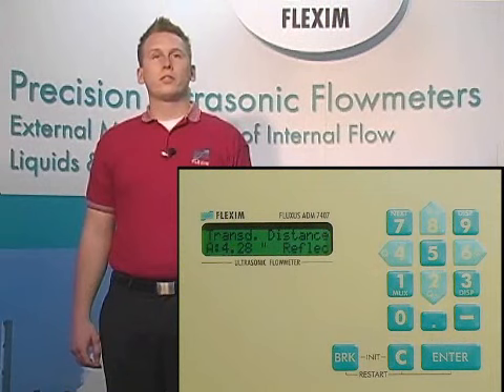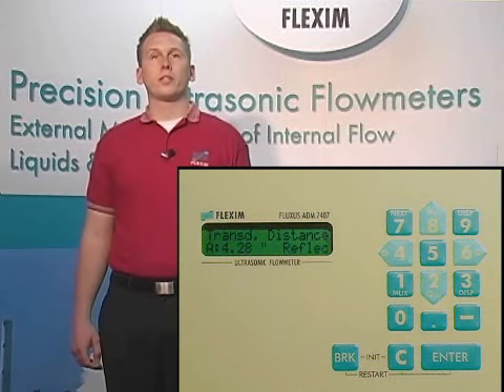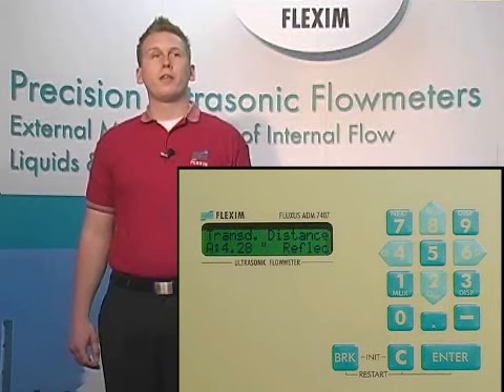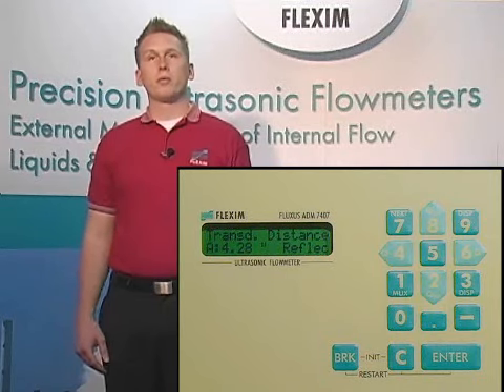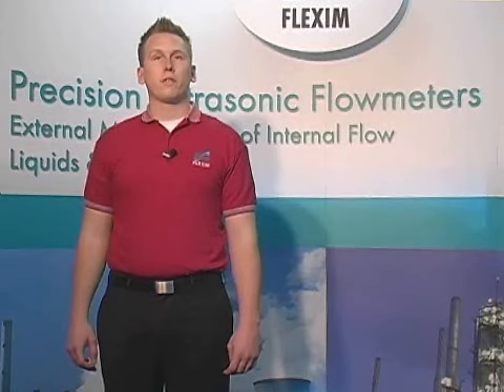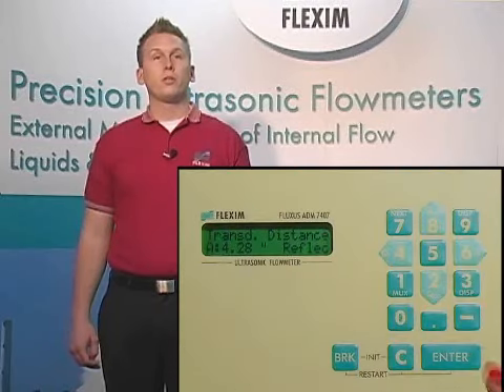This brings us to the transducer distance screen. Now that we told the meter how many sound paths to use, it's recommending the optimal distance to place our transducers apart on the pipe. And remember, since this is reflect mode, we'll have both transducers on the same side of the pipe. This makes it very easy to measure the distance the meter is recommending. We simply measure from the face of one transducer to the face of the other. So we need to actually install our transducers at the closest distance we can easily measure on a tape measure near what our meter is recommending. We try to stay within plus or minus a quarter of an inch of the meter's recommended distance, and then we will tell the meter the actual distance we place the transducers at. So now that we know where the meter wants us to put the transducers, we can hit enter.